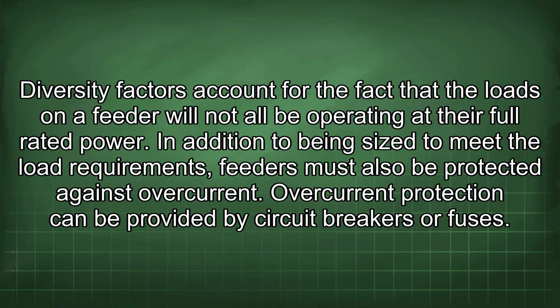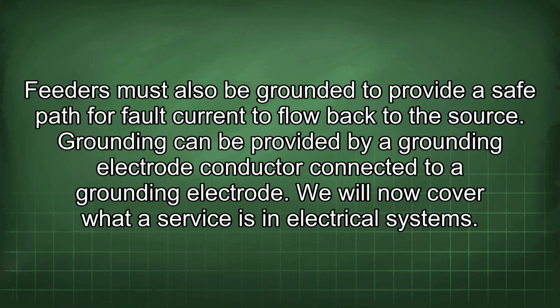In addition to being sized to meet the load requirements, feeders must also be protected against overcurrent. Overcurrent protection can be provided by circuit breakers or fuses. Feeders must also be grounded to provide a safe path for fault current to flow back to the source. Grounding can be provided by a grounding electrode conductor connected to a grounding electrode. We will now cover what a service is in electrical systems.